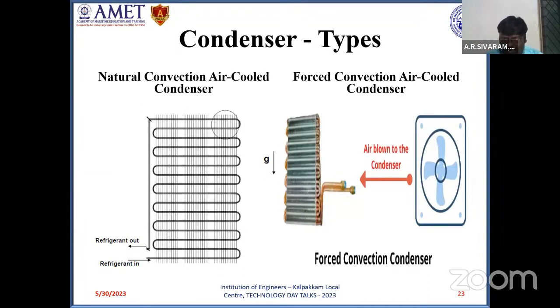So a natural convection air-cooled condenser uses atmospheric air, which can be found at the backside of refrigerators. Since the overall capacity of the system is quite less, it uses atmospheric air to condense the refrigerant from vapor state to liquid state. In the case of forced convection air-cooled condensers, we employ a fan to force the air, and the air strikes the outer surface of the copper tube. It takes the heat and the refrigerant condenses from vapor to liquid state. These are normally used in split type air conditioning systems and in quite a few industrial refrigeration systems.